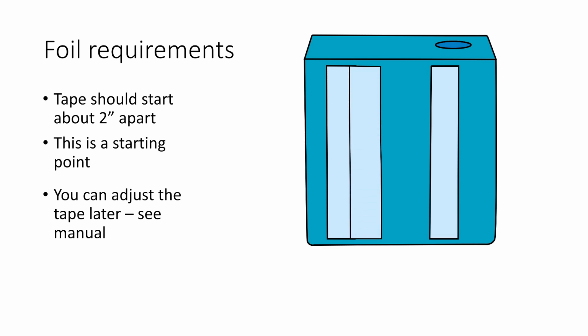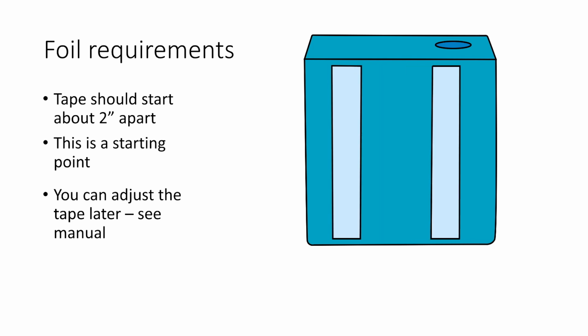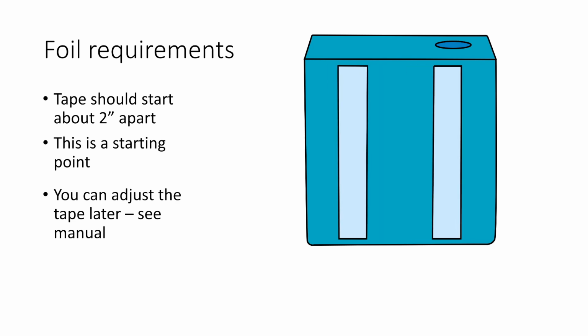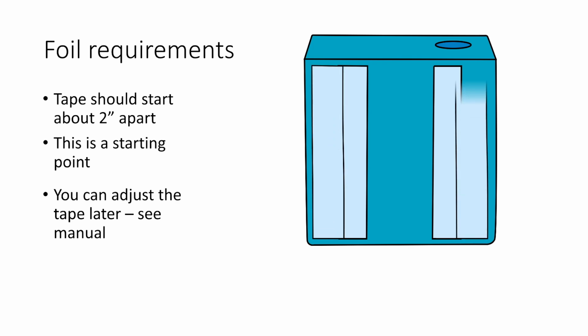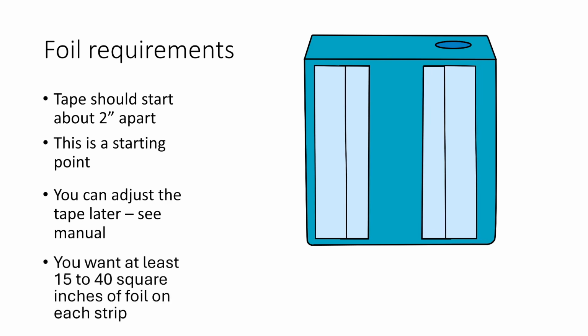If you have a shorter tank, you may find it will work better with the strips closer together. Taller tanks usually work with the tape a little further apart. Thicker tanks need the tape further apart and use more foil. Mark the top and bottom of the tank with consistent spacing. You want at least 15 to 40 square inches of foil on each strip. Once again, this can be modified after the installation and during testing.